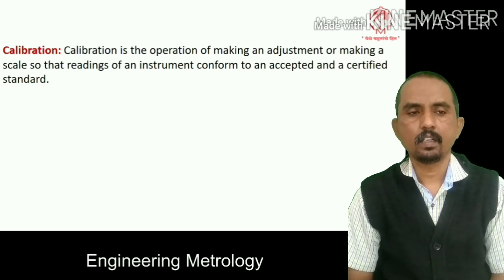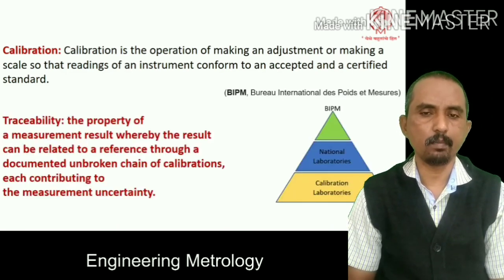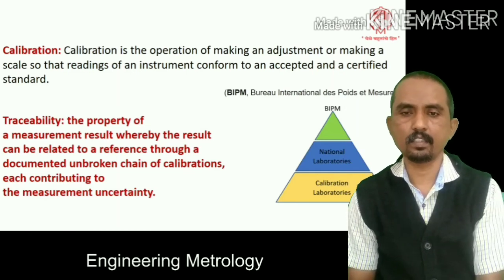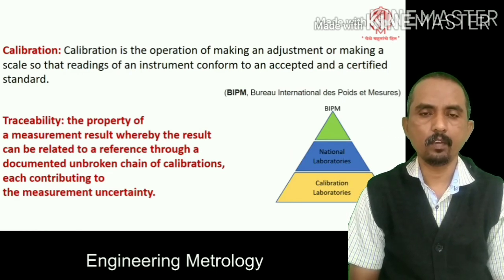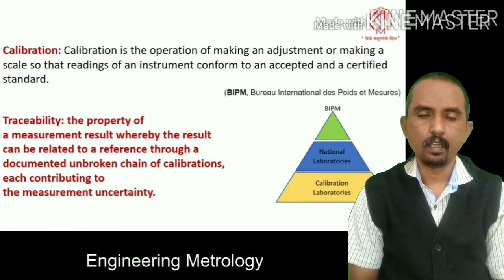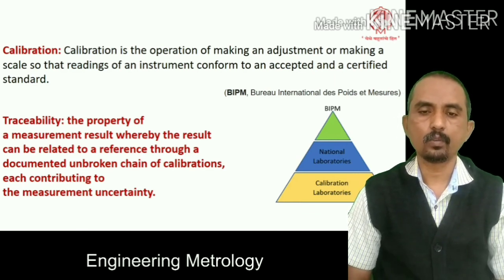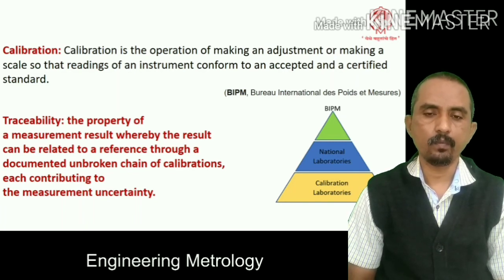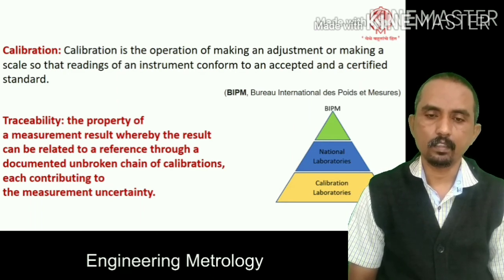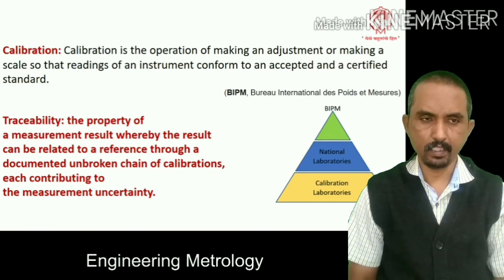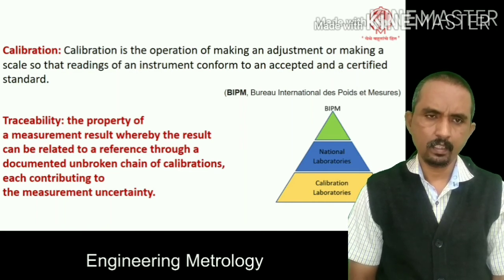Now this calibration is related with traceability. There is the Bureau International des Poids et Mesures, BIPM, and the standards from BIPM are traceable to the national laboratories of each country, and then from the national laboratories these standards are again traced to the calibration laboratories. That means traceability is a major part of calibration.